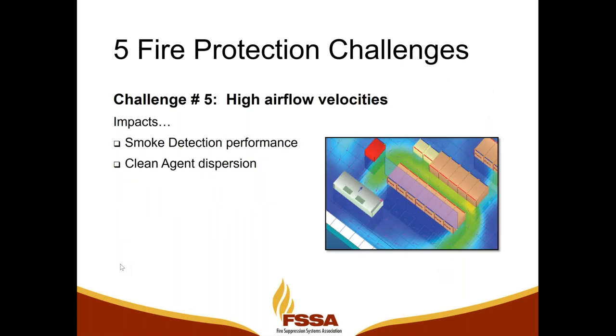And finally, high airflow velocities. This really speaks to how aisle containment affects smoke detection in these spaces. Because we're moving more air and we're better able to cool the IT equipment, the air change rate may increase, which increases the velocity of the air inside the contained aisleway, which will affect smoke detection performance in the way that the smoke moves, and it will also affect the clean agent dispersion in the spaces. Now we have new airflow patterns that we weren't originally anticipating, where we have data centers that get modified for aisle containment systems.